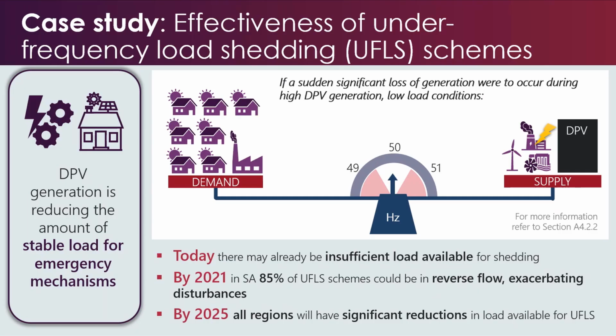To illustrate Rama's point on stable load for emergency mechanisms, we will look at a specific case study on the effectiveness of the under-frequency load shedding, or UFLS scheme, and why this is challenged as DPV grows. This is a protection scheme that operates at the distribution feeder with the intention to trip load in response to a sudden loss of generation and rebalance the seesaw and keep the system stable.